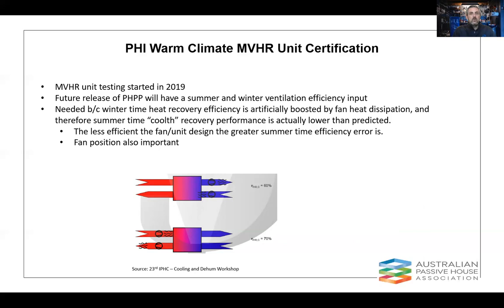And so for cool climates, where it's typically cold outside and we're trying to bump up the indoor temps, that heat dissipation has actually aided in the effective heat recovery efficiency. But when we're now talking warm climates, that actually has a deterioration on efficiency. And so it's important as PHPP is refined and the passive house process refined that we start to identify and reduce error in some of these regions. I think that's fairly straightforward there.